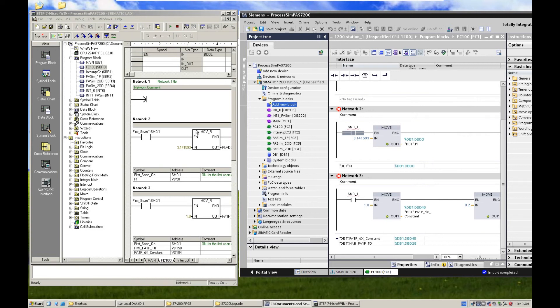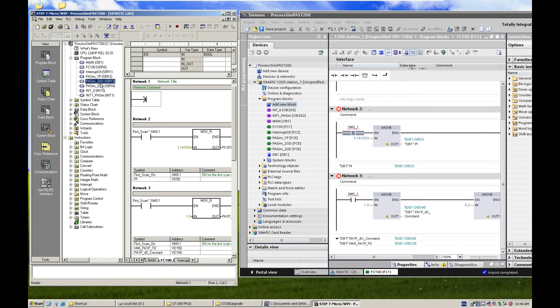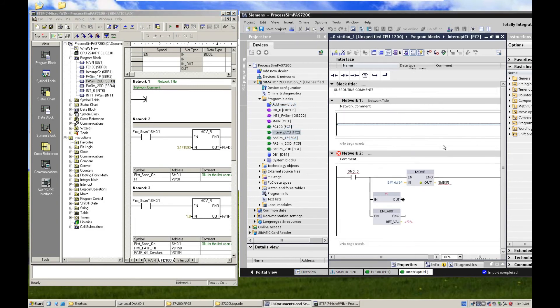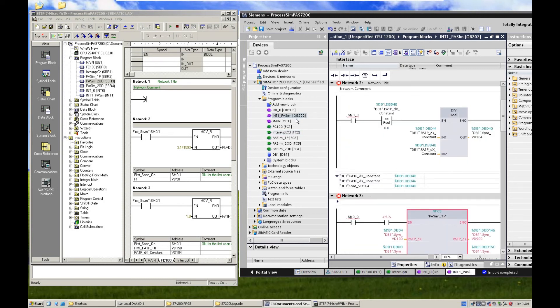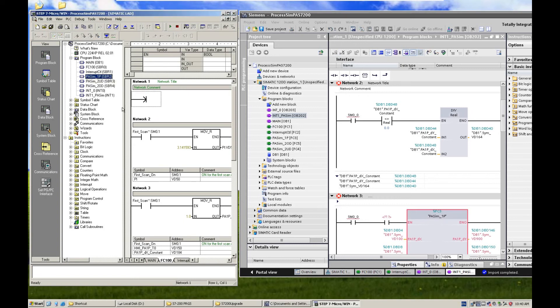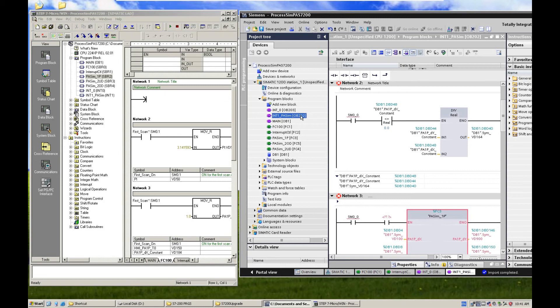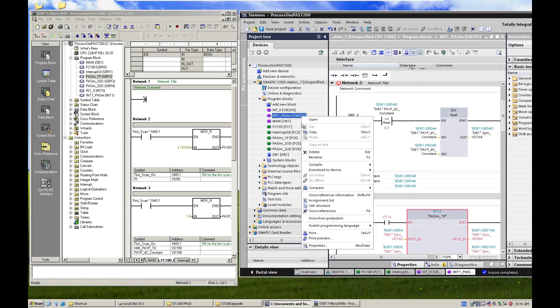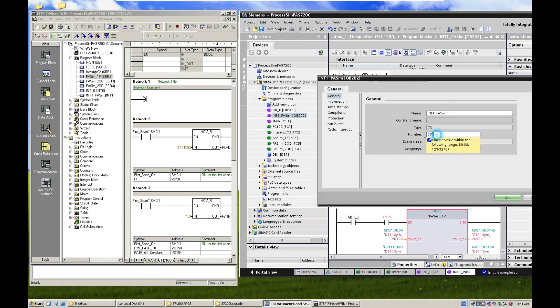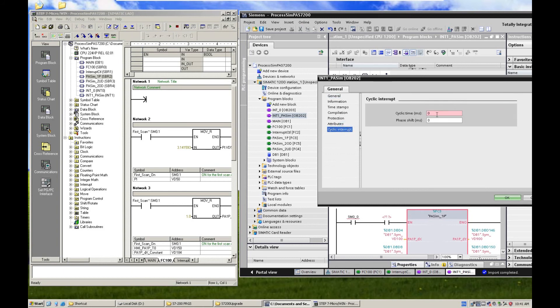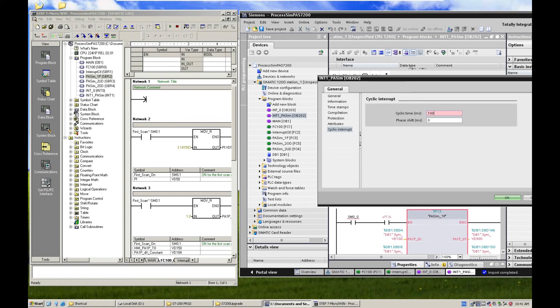And let's look at the cyclic interruption here. And this three function blocks were called by a cyclic interruption. And after converted, it generates one OB202 number. This is a cyclic interruption organization block. And this cyclic interrupt, the cyclic time, for example in the S7-200 controller that is 100 milliseconds. So from here we can type in the 100 milliseconds.